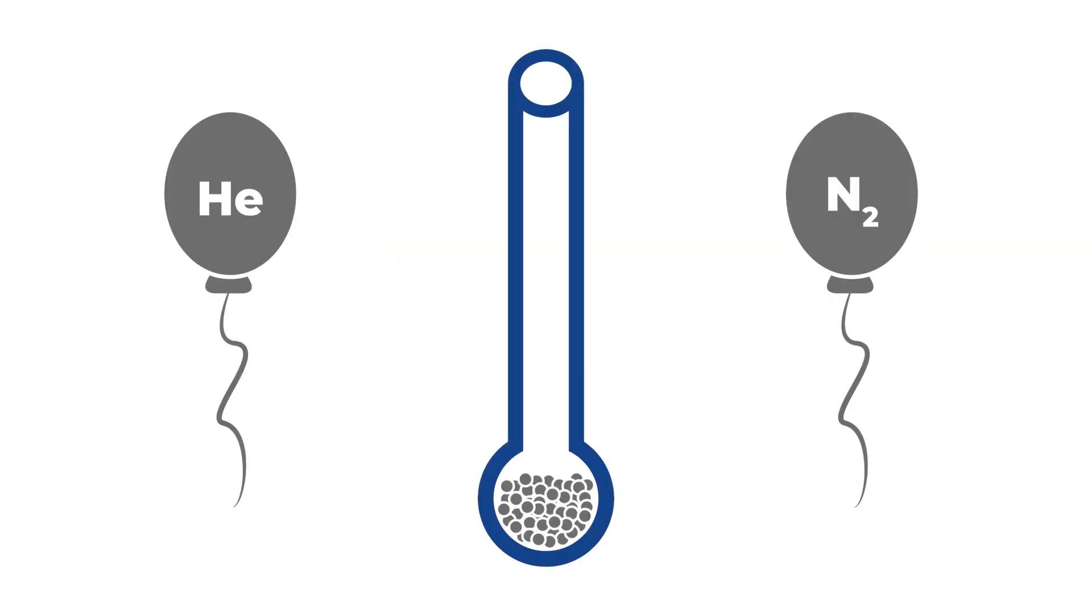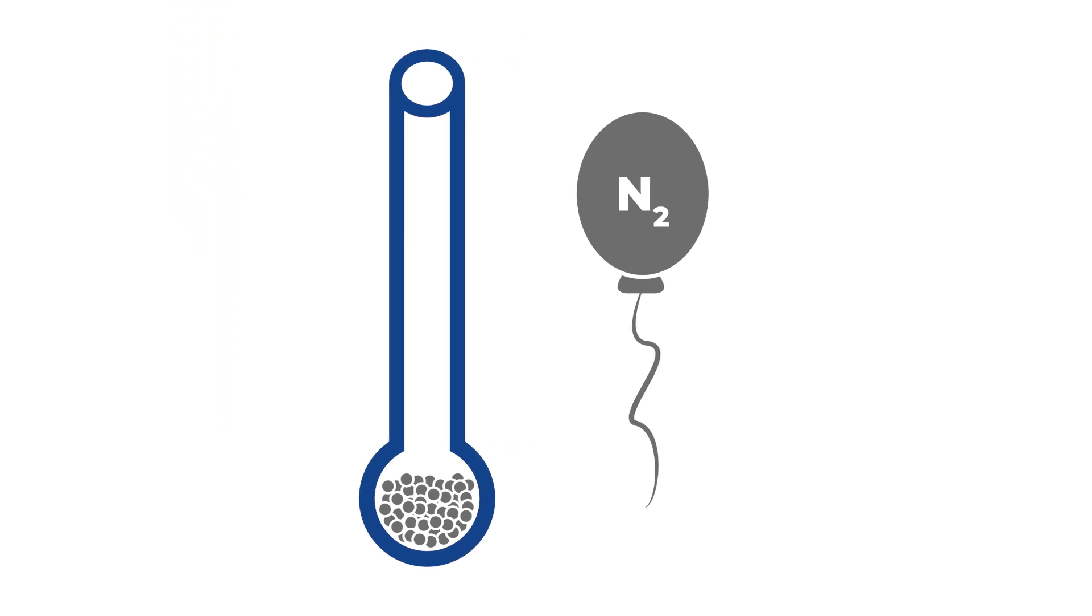Also, if the sample is being backfilled with helium after the degas, the buoyancy effect of helium on the sample tube mass should be considered. It is best to backfill with nitrogen to account for the empty tube mass that was filled with atmospheric gases.